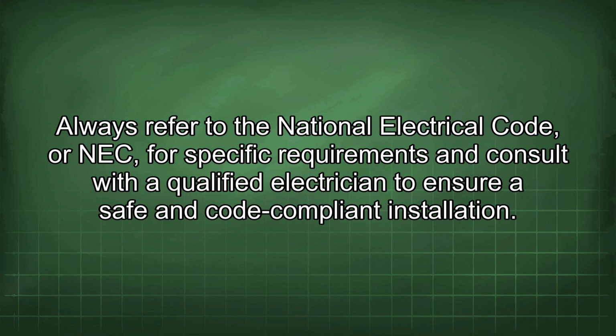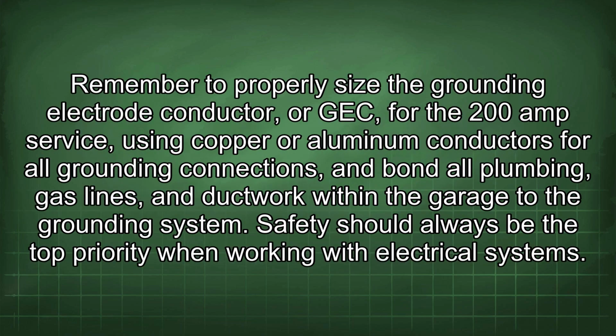Always refer to the National Electrical Code, or NEC, for specific requirements and consult with a qualified electrician to ensure safe and code-compliant installation. Remember to properly size the grounding electrode conductor, or GEC, for the 200 amp service, using copper or aluminum conductors for all grounding connections, and bond all plumbing, gas lines, and ductwork within the garage to the grounding system. Safety should always be the top priority when working with electrical systems.